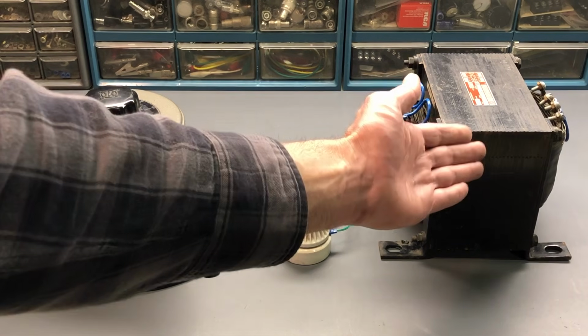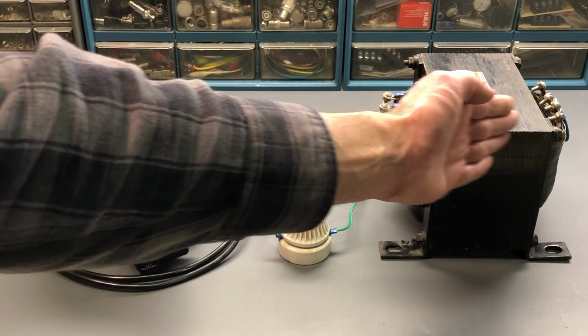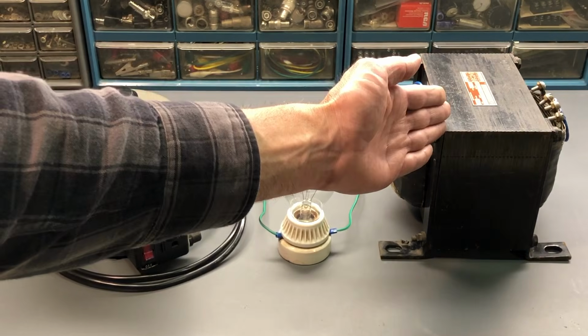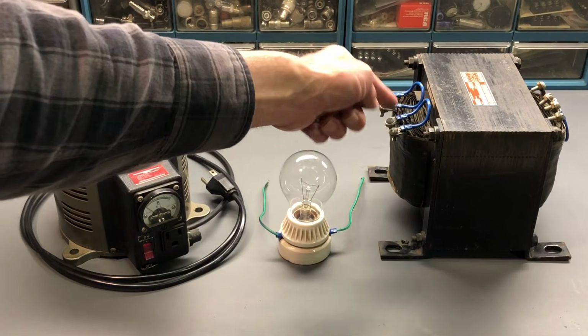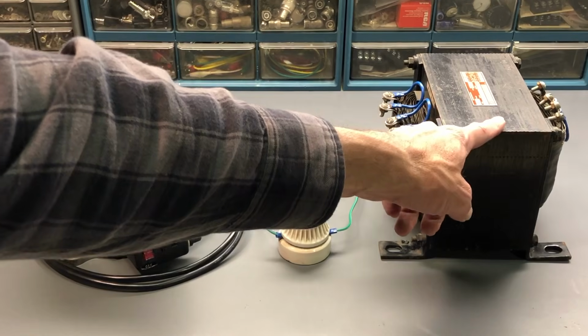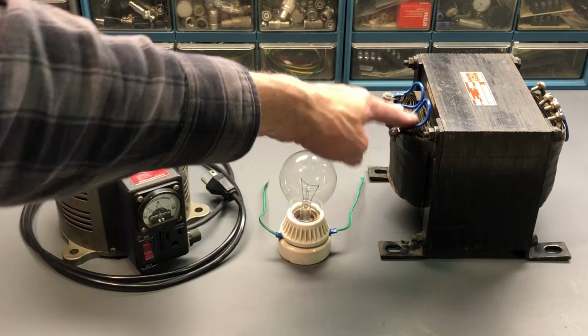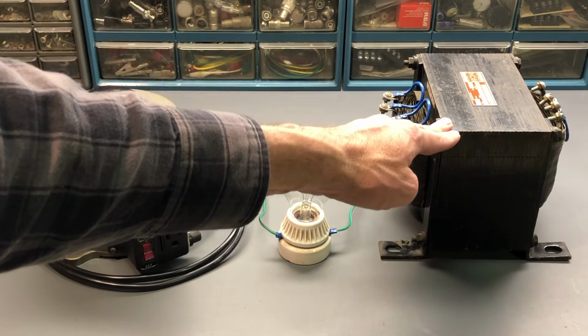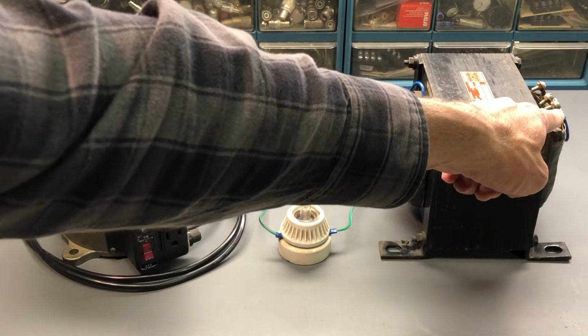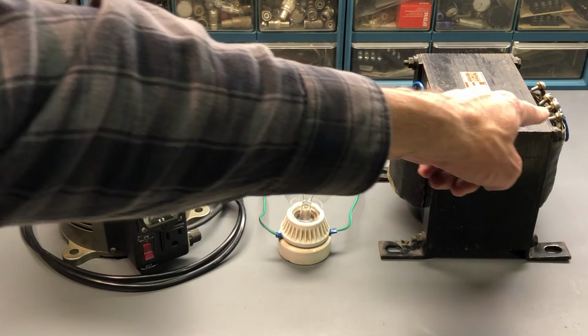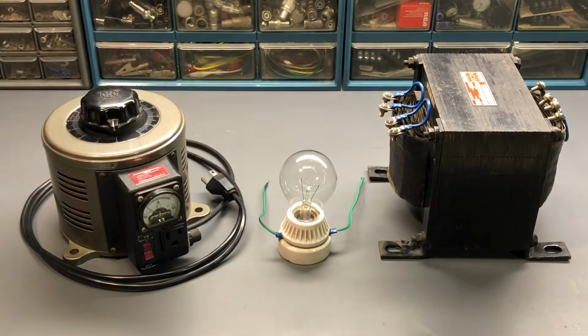A transformer like this is definitely an isolation transformer. It's very clear. You have a primary, you have a secondary. These jumpers on here are just selecting the taps. This can actually change the voltage depending on which taps you use, so it could step up or step down. I have it set for a 1-to-1 ratio, so the input voltage is the same as the output voltage. But there are isolation transformers that you can purchase that are not actually isolation transformers, so I'll show you that next.